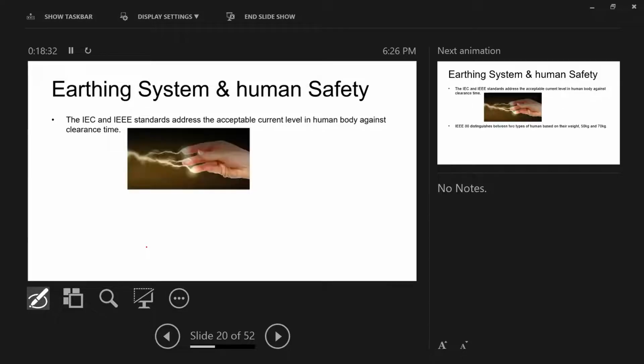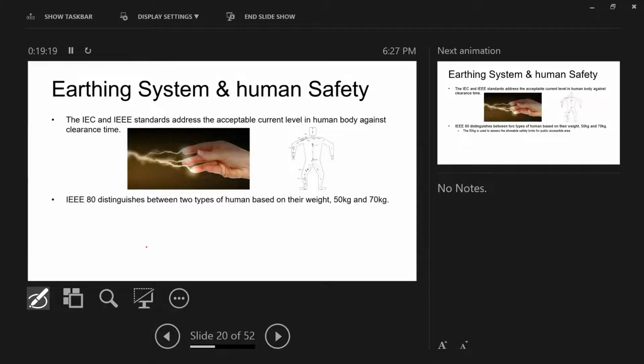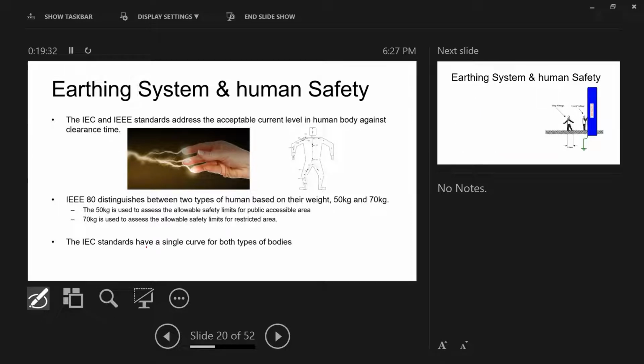A lot of standards talk about human safety, the human body. By the way, the resistance of a human is based on your skin. Break your skin, and because our human body is made of water, your resistance will be very low. That's why if you have any broken skin, you have a higher chance of permanent damage. The skin is what causes your resistivity to be high. There are European, American, Australian and Middle East standards, and all of them revolve around almost the same thing, except the American one distinguishes between two types of people: personnel of 50 kilogram and 70 kilogram. They say inside a substation, you must use the 70 kilogram equations, as you are allowed inside the substation. Outside the substation, you are only allowed to use the 50 kilogram equation because these people are more vulnerable.